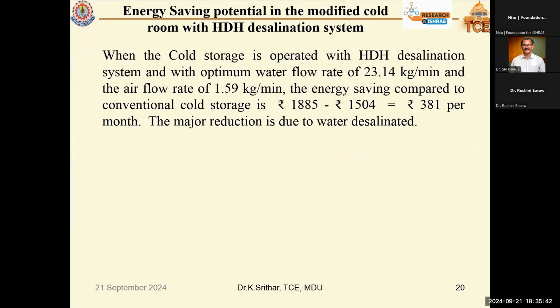And compared to the same energy saving potential, conventional will have an energy consumption of 1,885. When we have a particular mass flow rate, that is a higher mass flow rate of water and lower mass flow rate of air, it will have only an electricity bill of 1,504. Nearly, we are saving 381 per month. So by integrating two heat exchangers, in between the condenser and compressor, and in between the evaporator and compressor, we are saving 381 rupees per month of running cost. So that is the outcome of this proposed pilot plant.